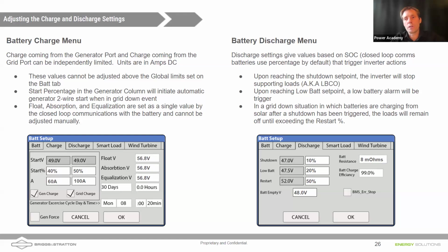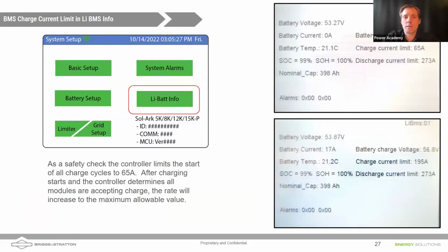The default values of the Sol-Ark actually come with lead acid values. I think it's a 42 volt shutdown value. So these are things that we have to pay attention to, and we'd like to absolutely have the right values for float, absorb, and equalization, as well as the shutdown values in the event of loss of communications. Technically, for systems that are stationary, there shouldn't be much that happens to trigger that, but it's always best practice to do that.